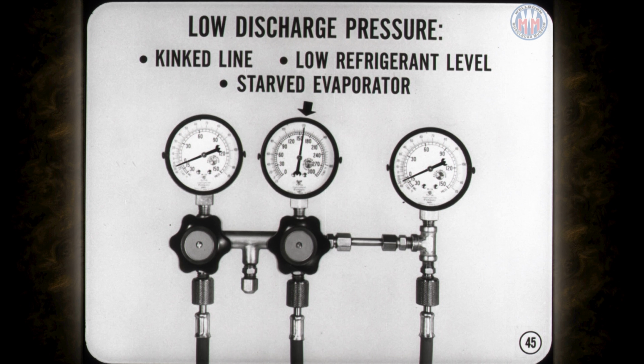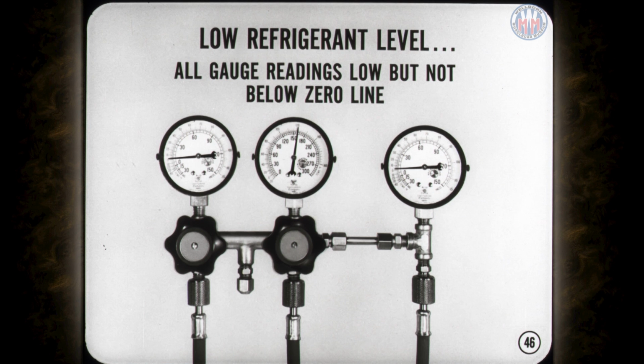Here you may find a kinked line, low refrigerant level, or a starved evaporator. Low refrigerant level can result from a slow leak or improper system filling. When the level is low, all the gauge readings are low, but the side gauges do not drop below the zero line. I'll tell you about checking the level farther on.